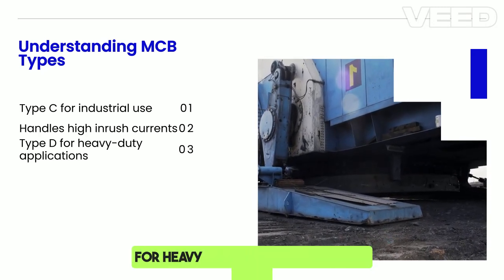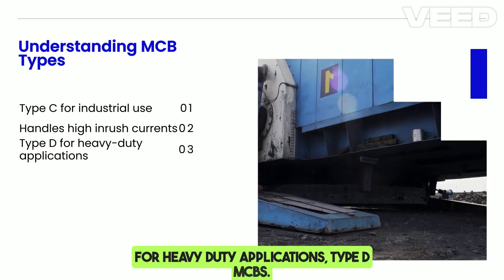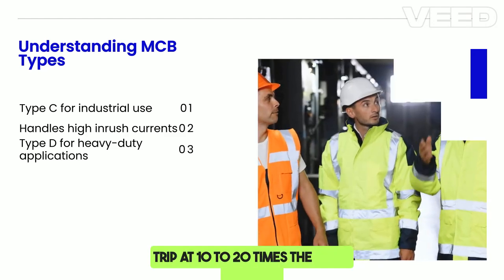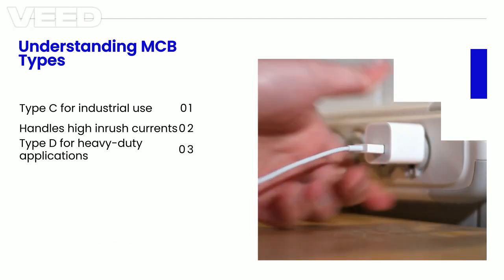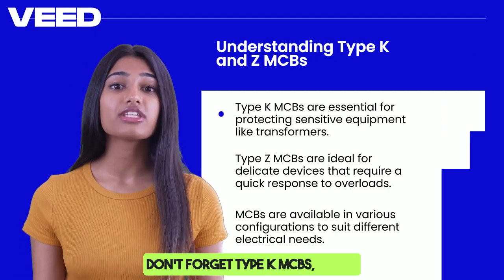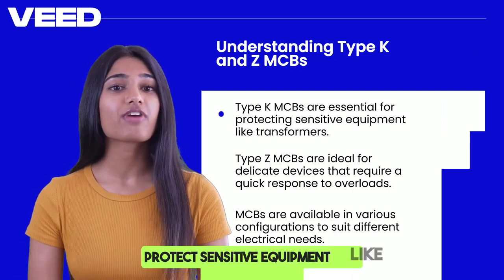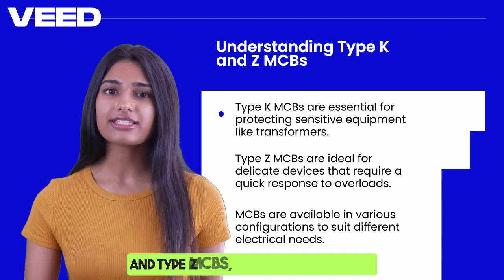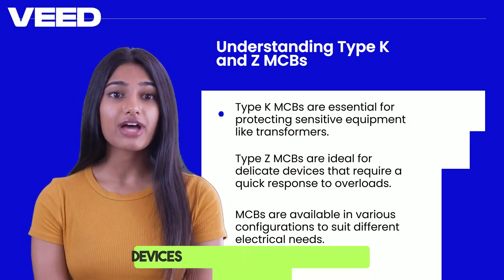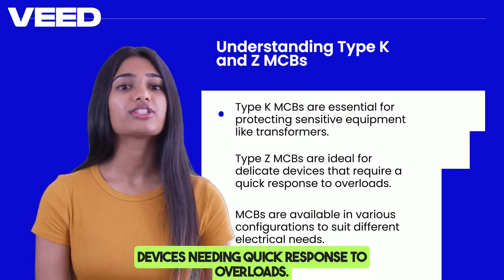For heavy-duty applications, Type D MCBs trip at 10 to 20 times the rated current, designed for large motors and welding machines. Don't forget Type K MCBs, which protect sensitive equipment like transformers, and Type Z MCBs, perfect for delicate devices needing quick response to overloads.